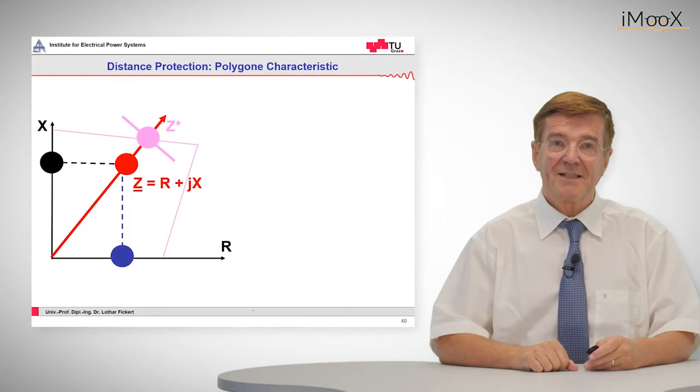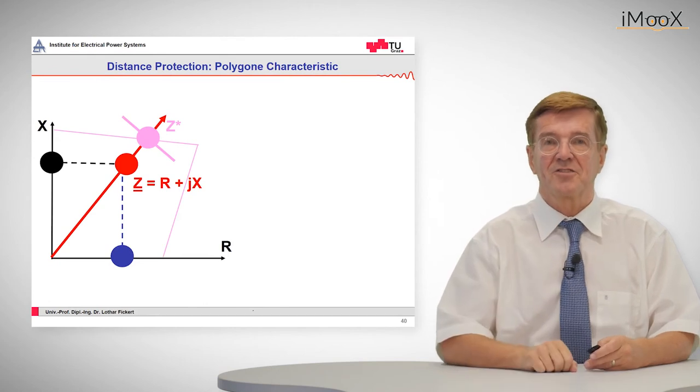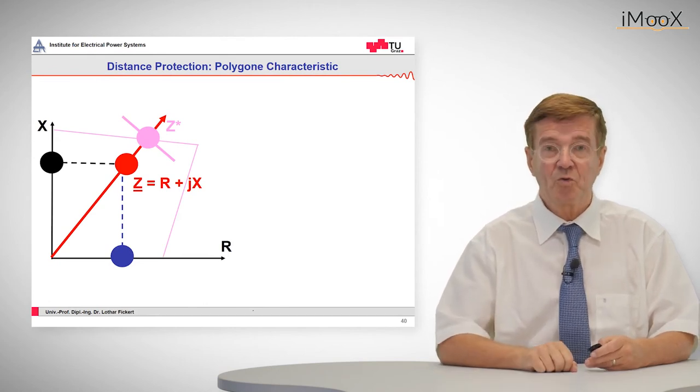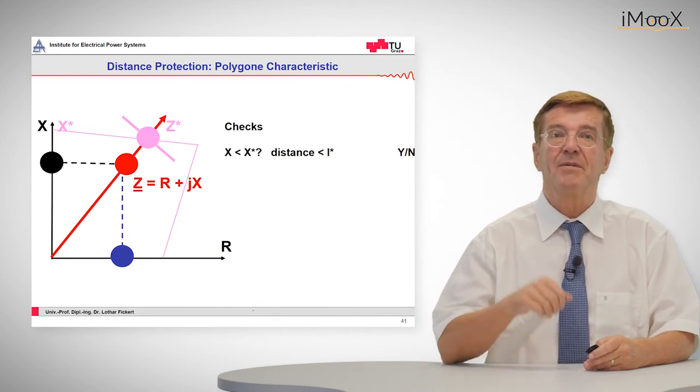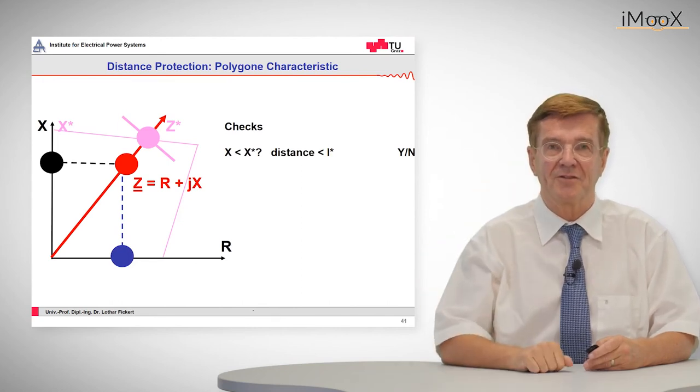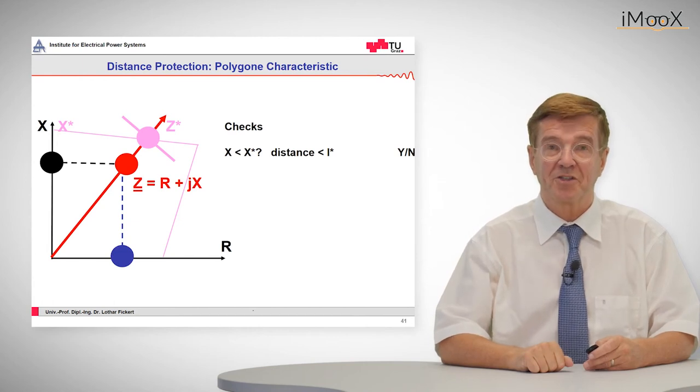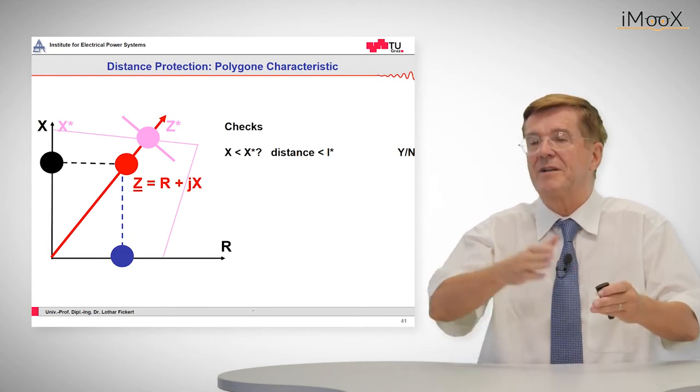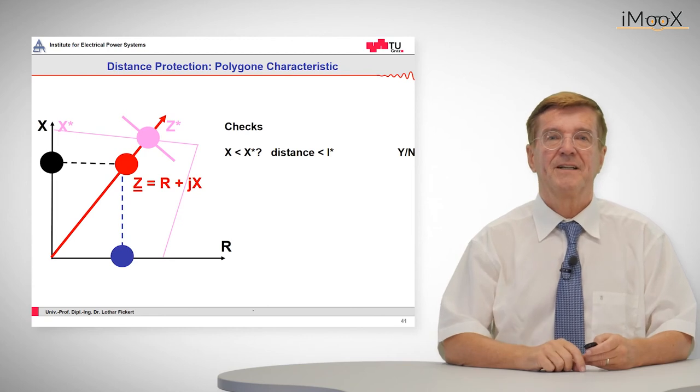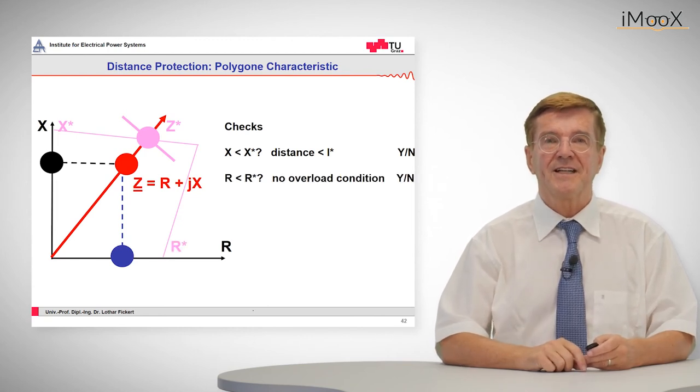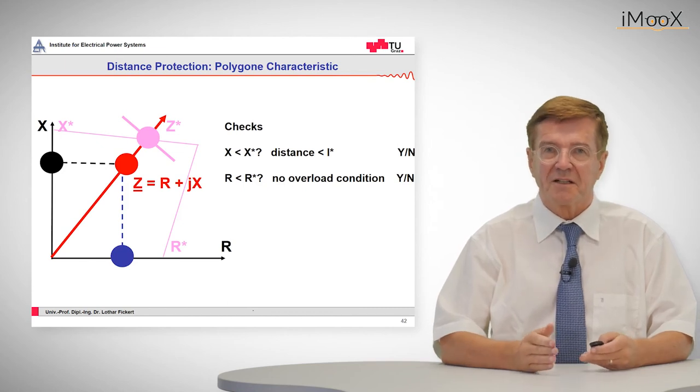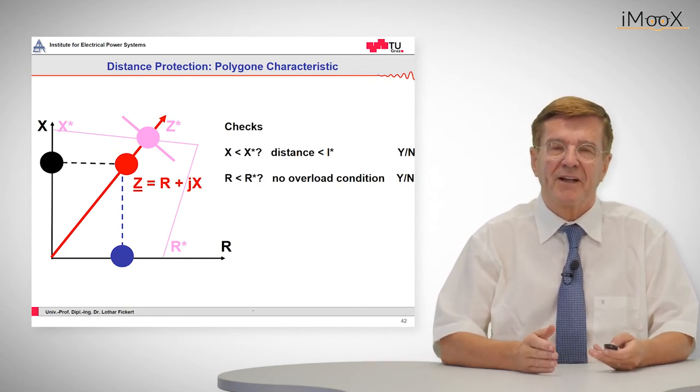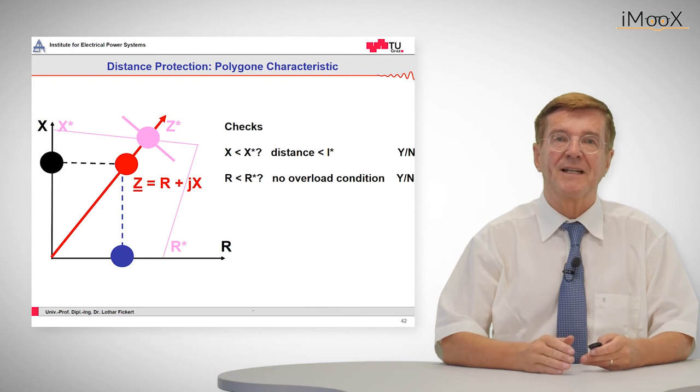So in the relays there are three conditions to be fulfilled. The most important one is, is the X that is measured by the distance relay, is it below this characteristic value, because X is proportional to the distance from the relay to the fault point. The next condition is, is the resistive part lying in an appropriate phase angle at appropriate place in this impedance plane.